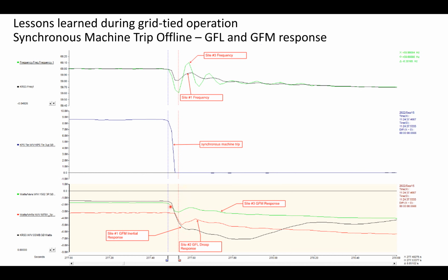However, the point to take here is that even though an inverter is in grid forming mode, it really matters what is going on in this black box of the algorithm of the inverter and how it's responding to frequency. You could have a manufacturer say that they're operating in grid forming mode, but it could have an inertial type response, or it could be following just a droop response. And you'll see that here. We've got 2 vendors connected, and they're each putting out different types of fast frequency response to system frequency going out of the deadband.